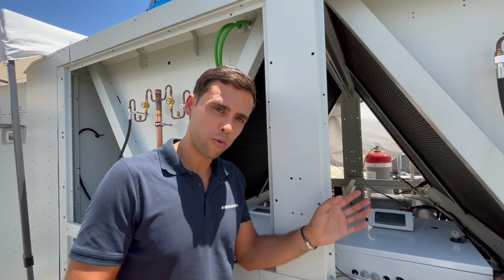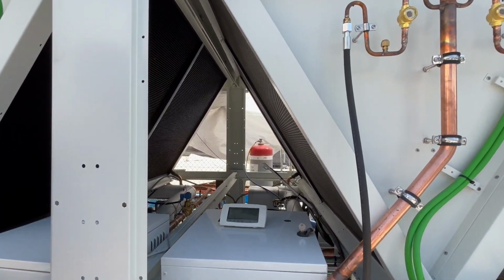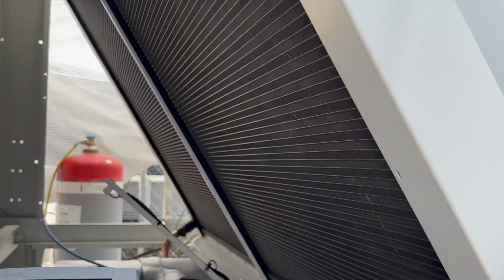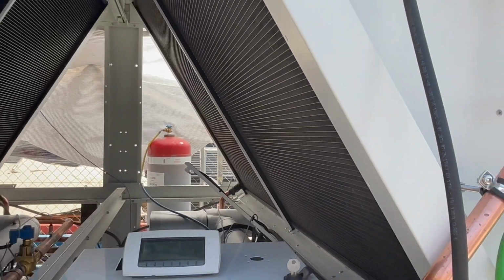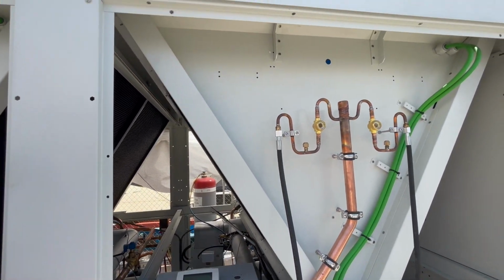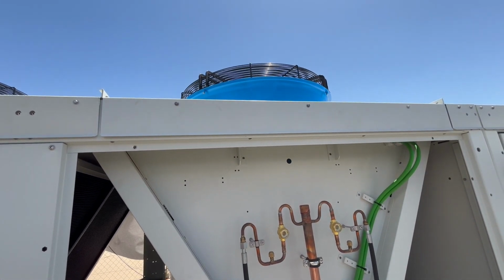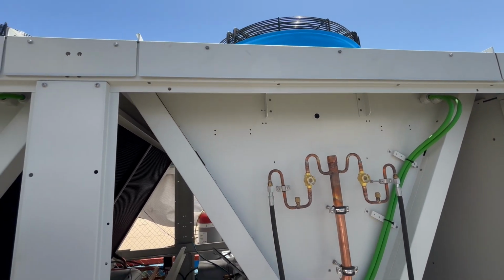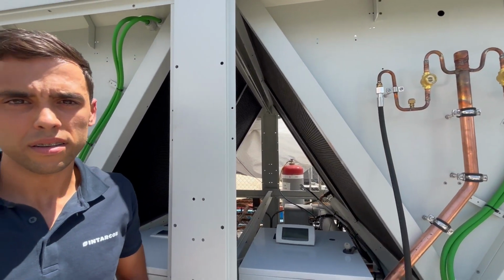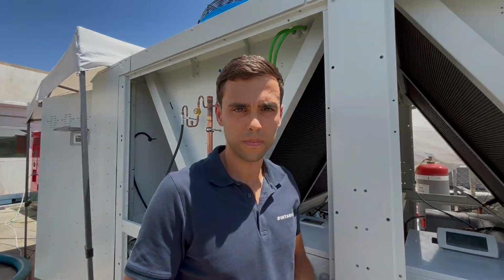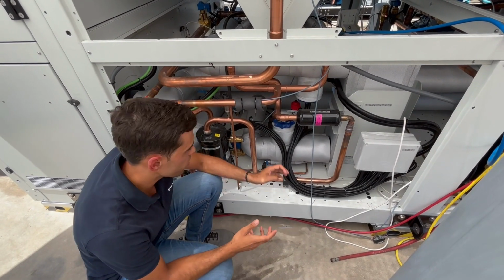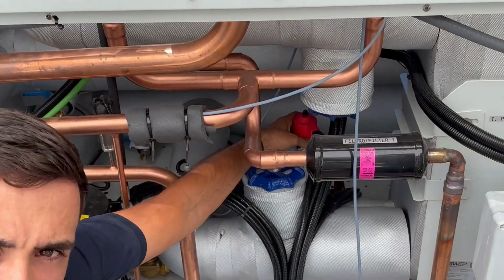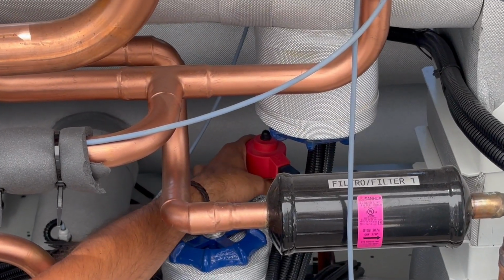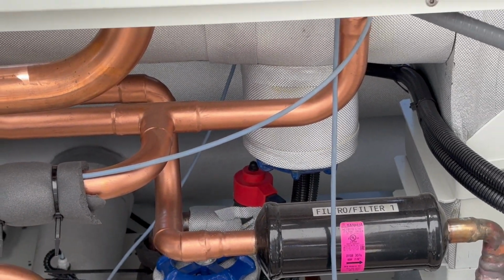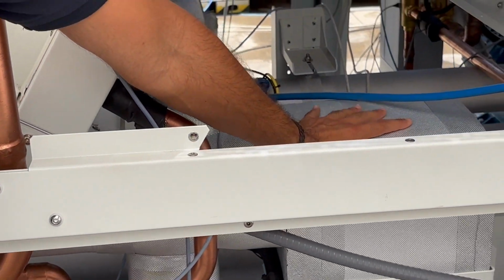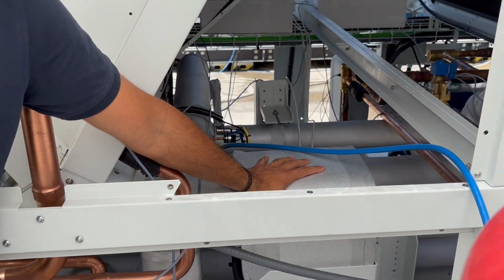On the condenser side, we have got microchannel coil with polyester powder coating treatment that we combine with axial electronic fans, with which we are able to vary the airflow through the condenser to adapt to the heat transfer demand. On the low pressure side, we have got an electronic expansion valve that regulates the mass flow of the refrigerant through the circuit. In addition, we have got a plate heat exchanger as evaporator made of stainless steel.